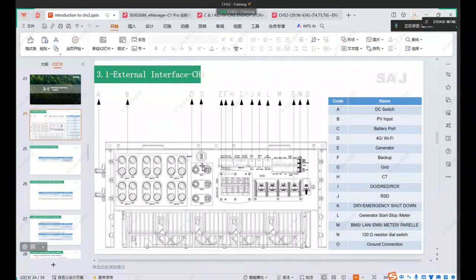And the code C is the battery port. This is already connected in our factory. And this is the 4G. Use our 4G and Wi-Fi to connect. Sorry, can I ask a question? Do we need a combiner box for every single string? Combiner box. Yeah. Actually, in the project, you better have a combiner box for that. For every string. Yeah, but it's not necessary, but it's better to do that. Okay. So we do have the protection inside. Yes, we already have the protection inside. Like some DC protection. Yes. Or fuses. Yes, and the arc protection.